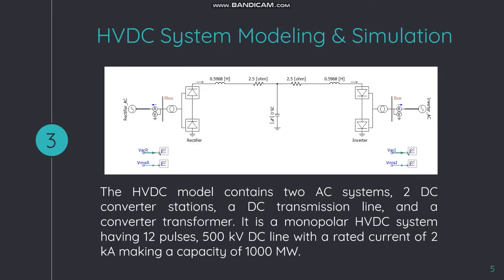This is the HVDC system model on PSCAD, obtained from an example file. The CIGRE model is a benchmark model available on PSCAD. This model contains two AC systems, two DC converter stations, a DC transmission line, and converter transformers. It is a monopolar HVDC system having 12 pulses, a 500 kV DC line with a rated current of 2 kilo-amps, making a capacity of 1000 megawatts, all shown in this figure.